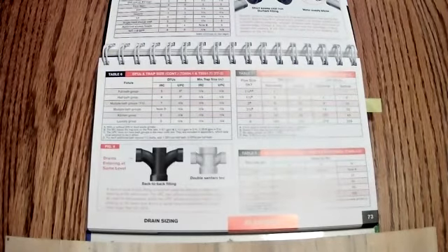Now, as we do that, we're going to be looking down here at some of the different types of fittings. These are back-to-back fittings, and you need to know what size fittings you're looking at and what they're called. A back-to-back fitting, if you read down there, should be used for fixtures or trap arms entering at the same level. The IRC also allows a double sanitary T to be used for this purpose, while the UPC allows it only for branch drains entering at the same level and into the barrel. The minimum pipe size is 2 pipe sizes larger than the inlets.